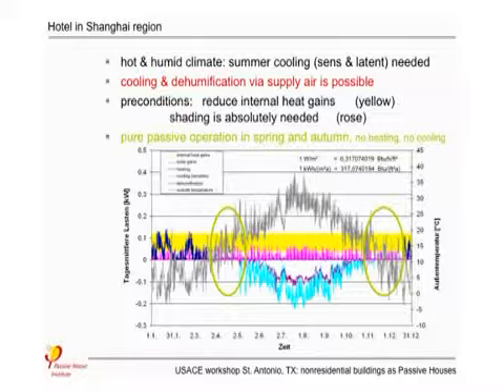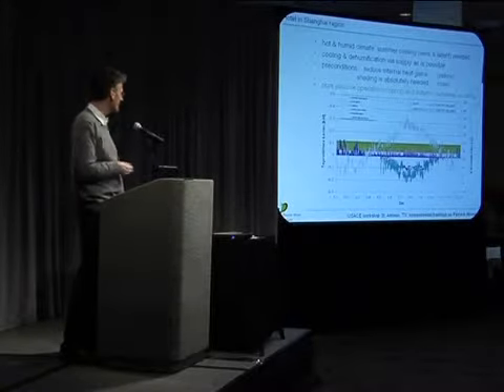Well, and then in the single apartment or maybe office, part of the office, you install a conventional split unit, or the internal part of the split unit, like here in the hotel. But what is important, you drive it not with 6 times air change rate per hour, but you may only use 2 times per hour. And therefore, the noise emission of this device will not be as high as a standard split cooling device. And so we think the acceptance of this low power cooling device will be much higher than before with the very noisy cooling devices.